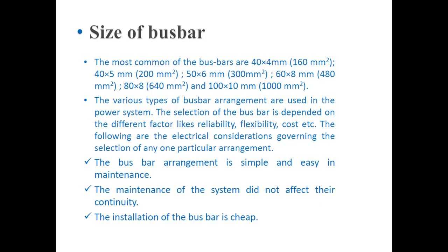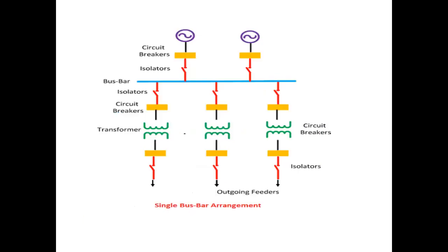The bus bar arrangement chosen should allow easy maintenance without affecting continuity of supply. Different types of bus bar schemes include: single bus bar scheme, single bus bar with sectionalizing switches, double bus bar, double breaker, main and transfer bus scheme, double bus single breaker scheme, and ring bus scheme. The choice depends on cost, safety, reliability, sub-transmission voltage level, and substation location.